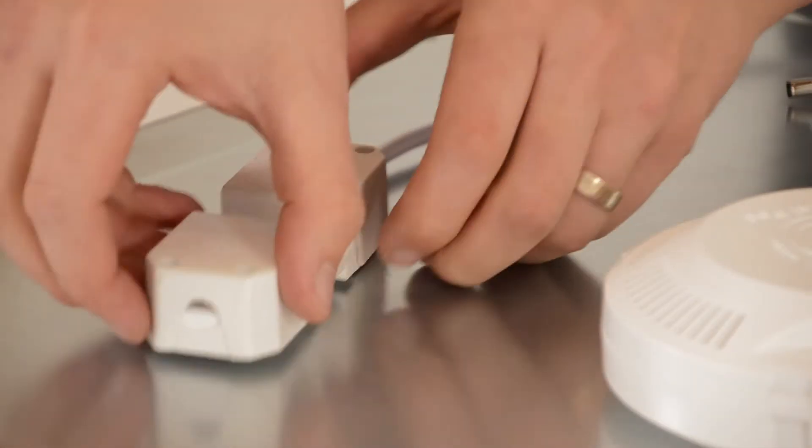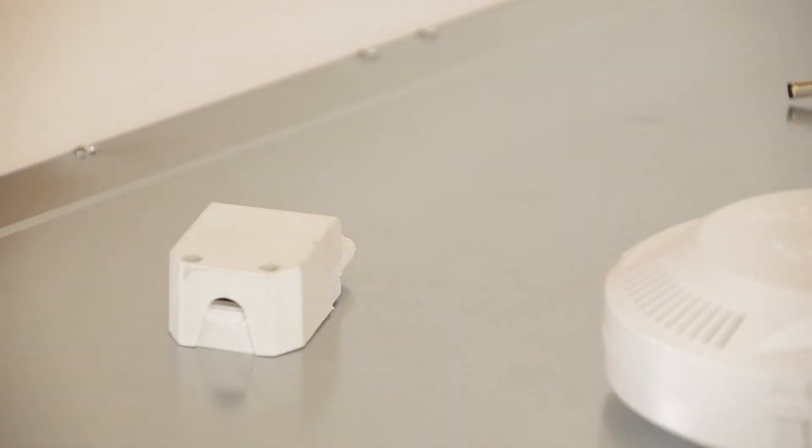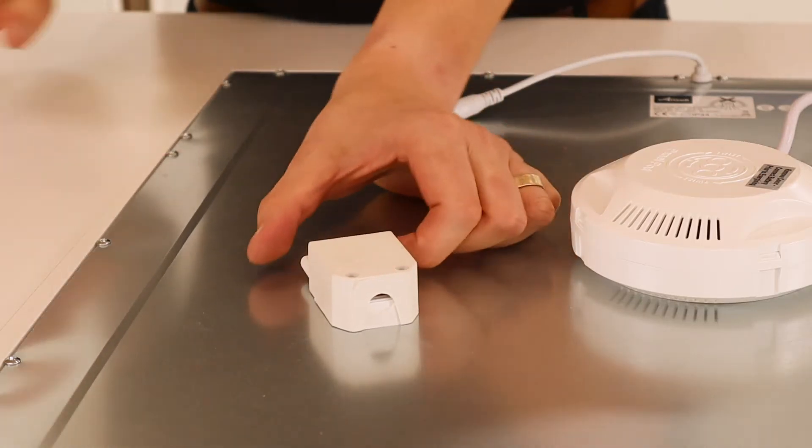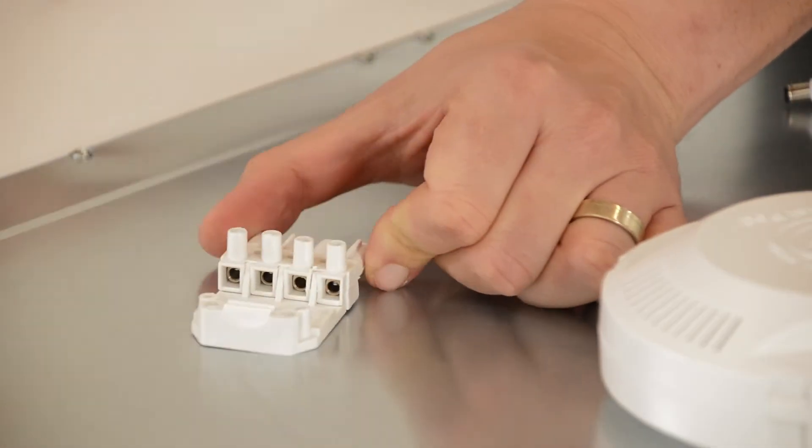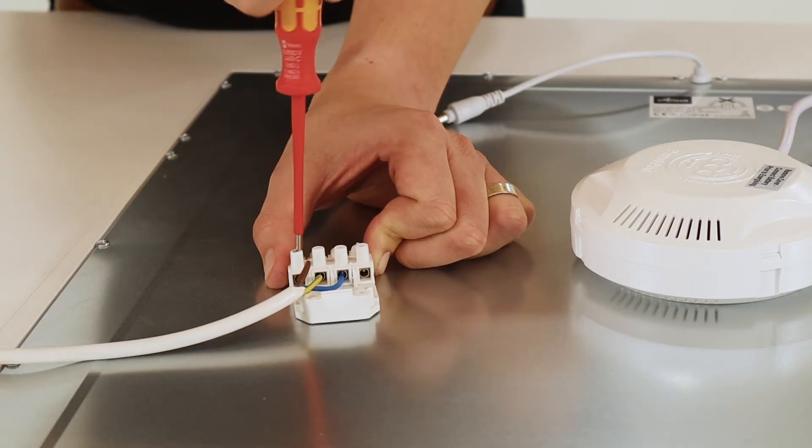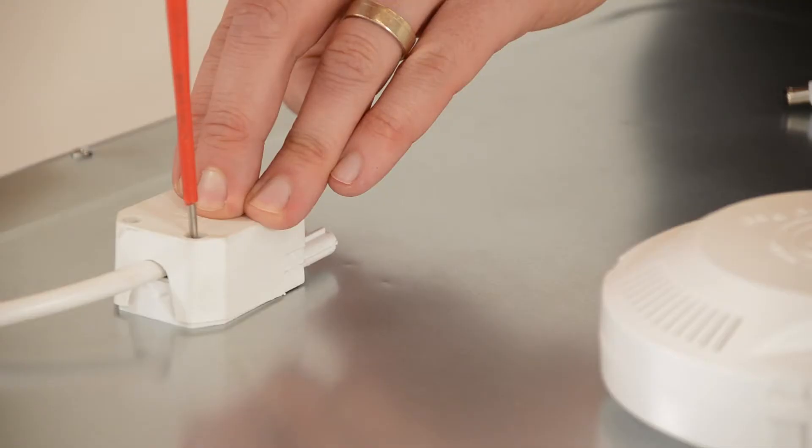The PanelPod is pre-wired with one meter of three-core cable with a four-pole male terminal connector for connection to the PanelPod and the panel driver itself. The PanelPod also comes with a three-pole connector for the incoming mains. Both connectors allow for fast connection.